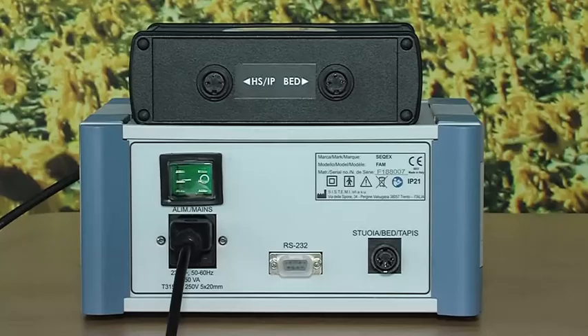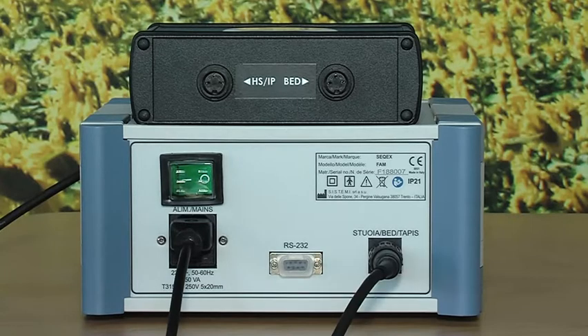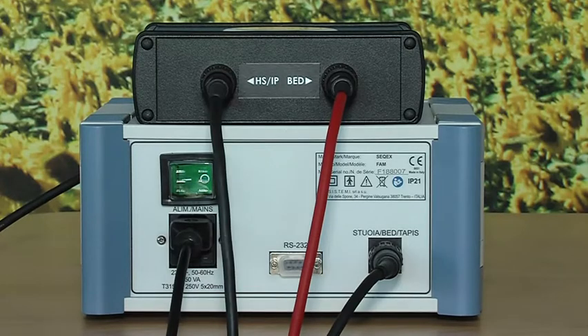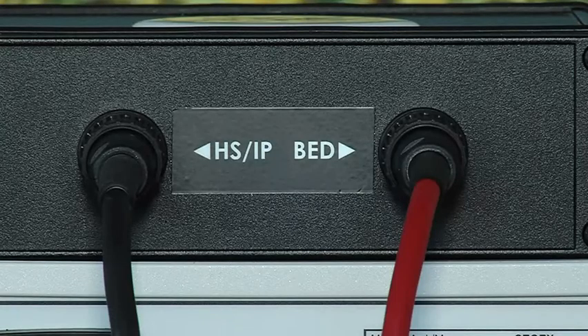Now we will see how to connect and use the accessories. To use the mat and an accessory at the same time, connect the signal splitter to the bed socket on the back of the unit. Then connect the mat to the bed socket on the splitter and the accessory to the HS/IP socket. It is important to remember that the bed socket must always be connected.